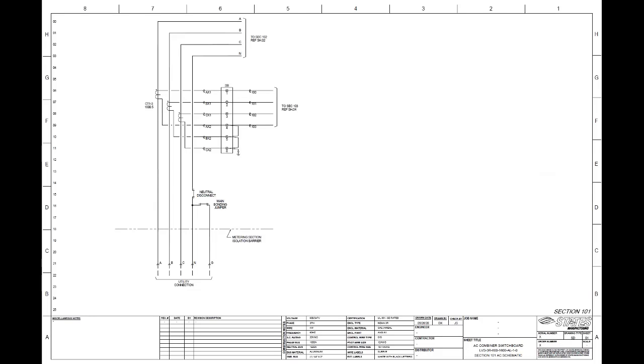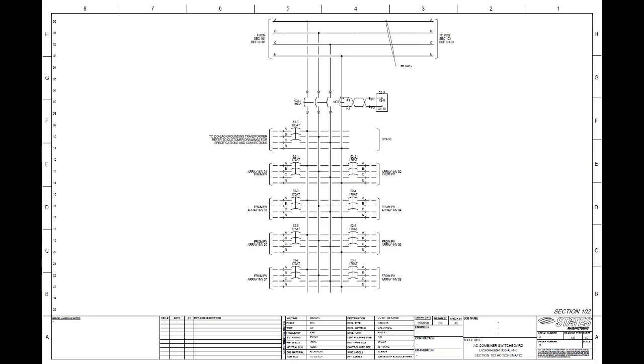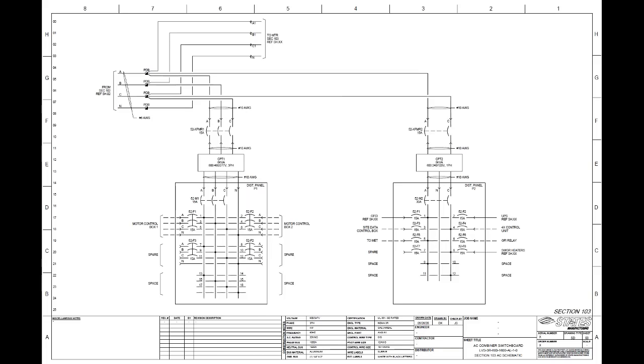As I said, flow through the different 3-line diagrams, group mounted breakers, the main breaker, and then any of the station power. We, in this case, even can do multiple station control power transformers. And oftentimes we see this being the case because you'll need one that is 600 down to 480, 277 if there's different motor control. I think they had some different fans on this installation, tracking motors. You know, maybe 480 volts required to power up different parts of the solar string as they rotate the panels to get the best angle to the sun. And then you still need to get down to 120, 240 to either power up a meter, a protective relay, or the customer's metering system.